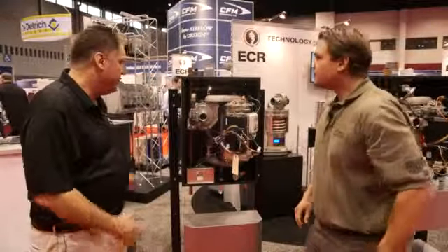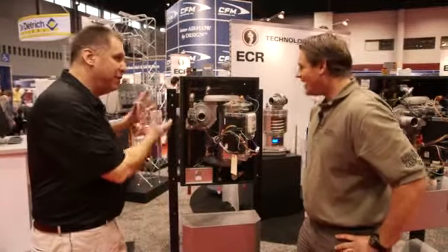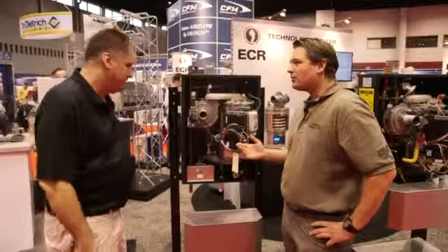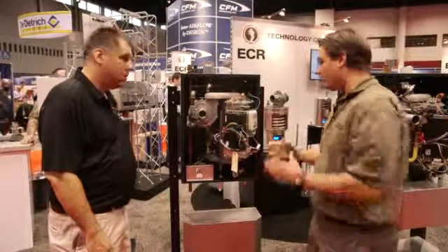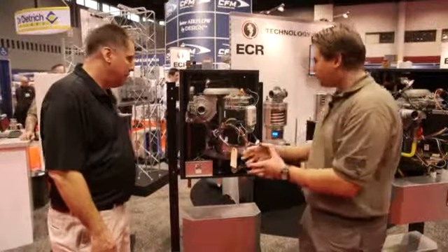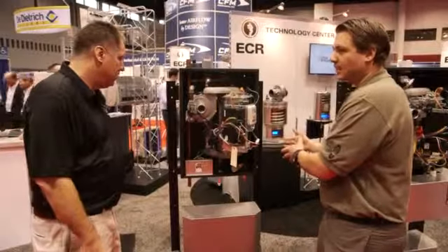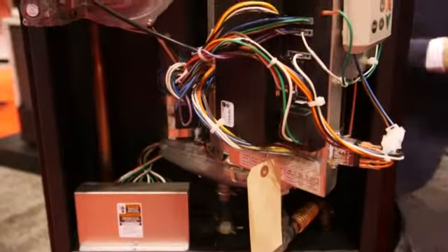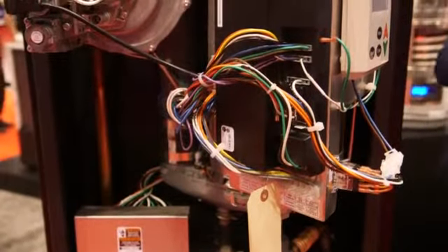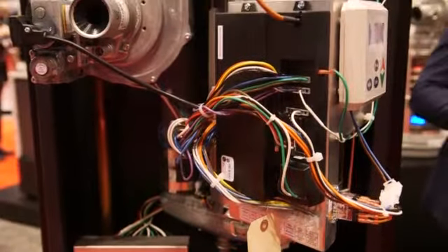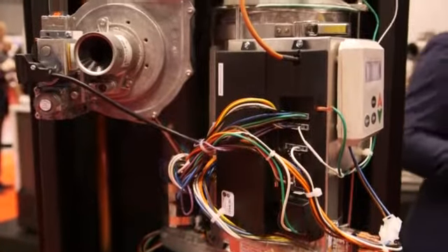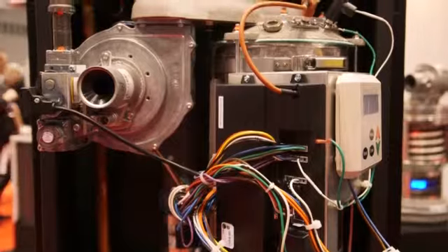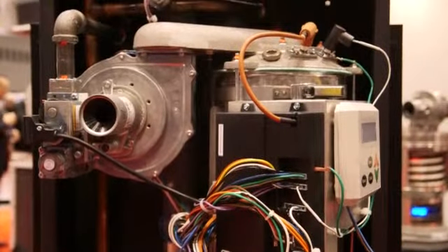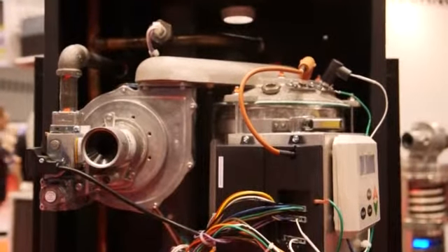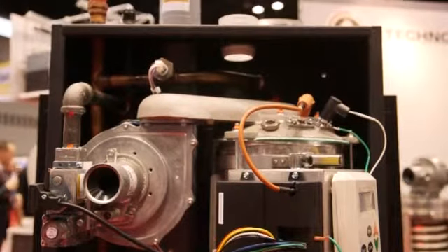So I'm familiar with this boiler, but this looks a little bit different. Tell me what's different about this one. This is the entry-level model. What we've done is some guys prefer doing their own primary, secondary piping, or they prefer using a hydraulic separator. So we've taken the internal primary, secondary out of it and put it outside the boiler. Another feature that we've done here is we've taken the gas line, instead of going out of the bottom, it actually comes out of the top. Some contractors do like that because a lot of gas lines are overhead. Sure, that simplifies the piping.